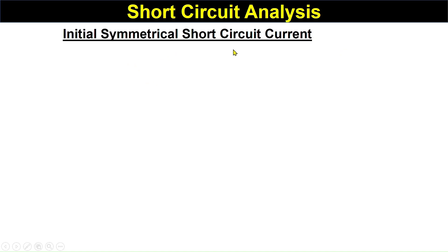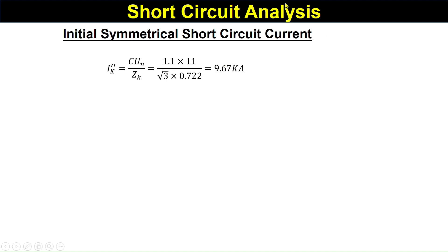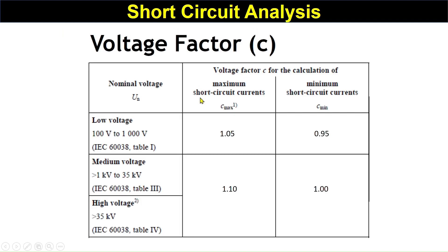Now we calculate the initial symmetrical short circuit current I_k''. The formula is I_k'' = (c × U_n) / (√3 × Z_k), where c is the voltage factor (1.1) and U_n is the nominal voltage. We calculate on the 11 kV side, so I_k'' = (1.1 × 11 kV) / (√3 × Z_k), which gives approximately 9.67 kilo-amperes.